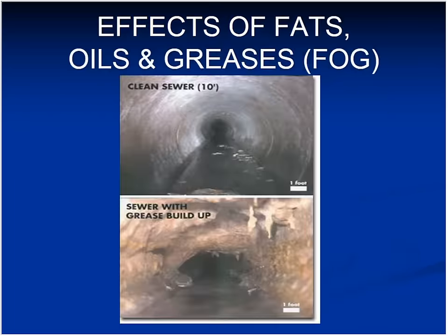The other problem, particularly during heavy rain periods, is what we refer to as fats, oils and greases, or FOG. Grease and oil should not be dumped down into the system. Baking grease should not go down there. You might say, well, I'll run the hot water, throw a little Dawn in and chase it out. At some point, it's going to hit some cold pipe and plate out.